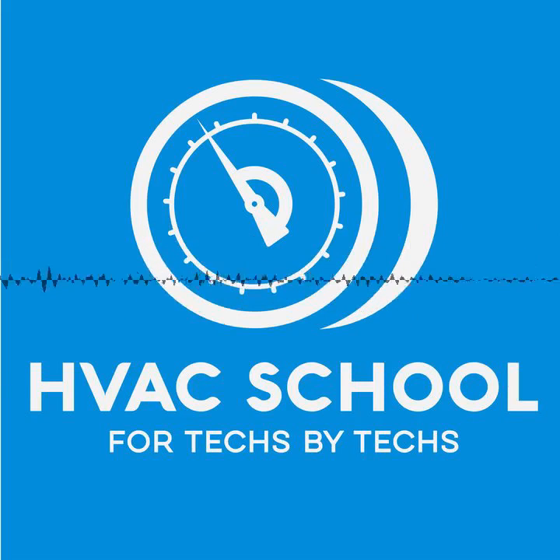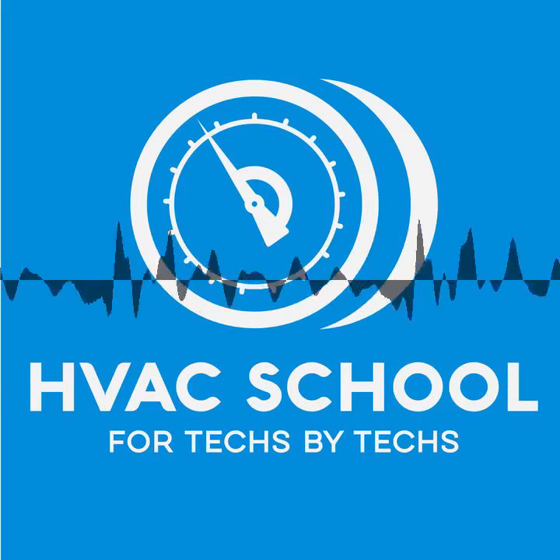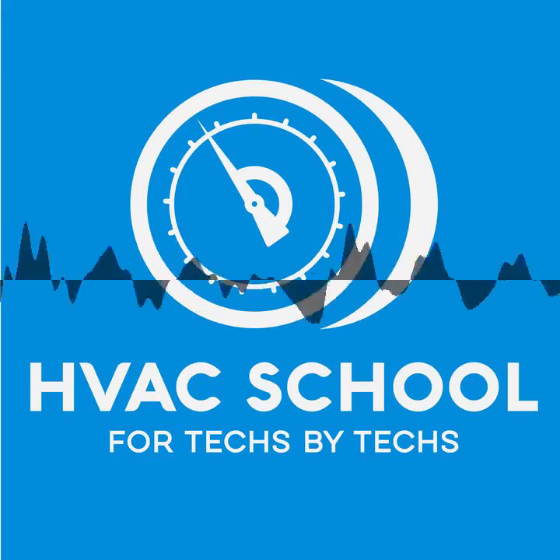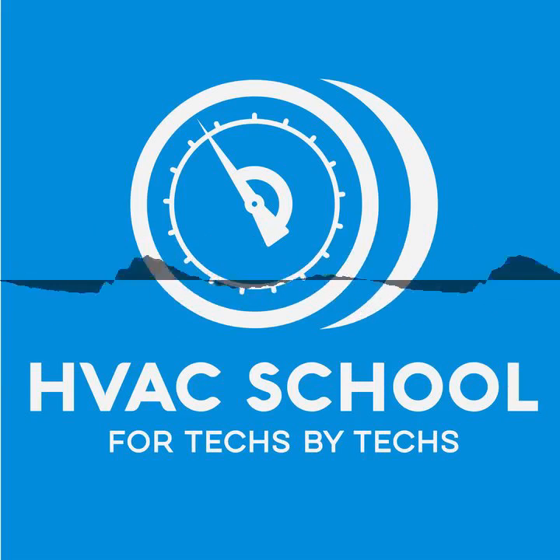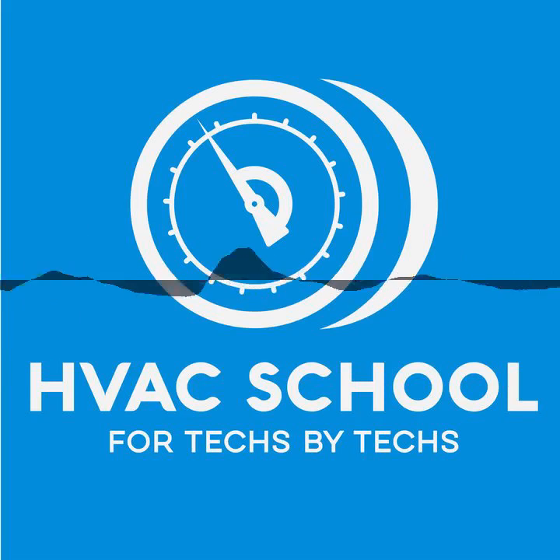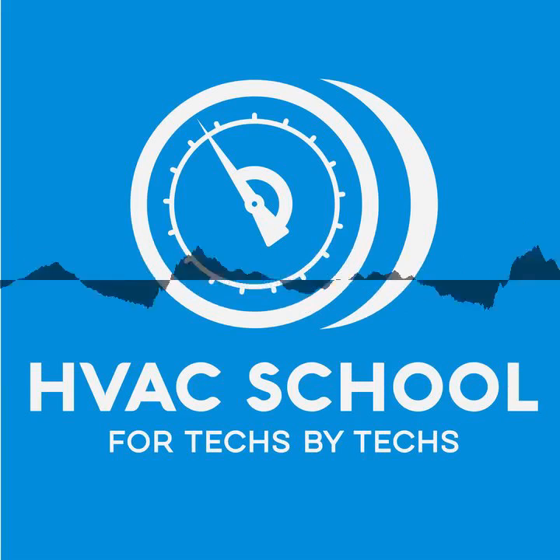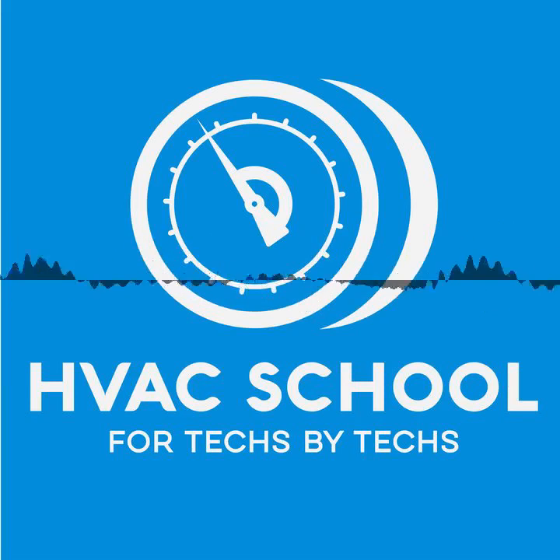The next thing that I want to mention is comfort bandwidth, and this is actual dry bulb temperature bandwidth. With variable speed technology, you don't have to keep bumping top and bottom of the limits. You don't have to be running a 3-degree temperature bandwidth. You can nail it directly on a set dry bulb temperature if you want to, which is a benefit from a comfort standpoint. Because when people are in a space and the temperature keeps changing up and down 3 degrees, they're going to be uncomfortable.